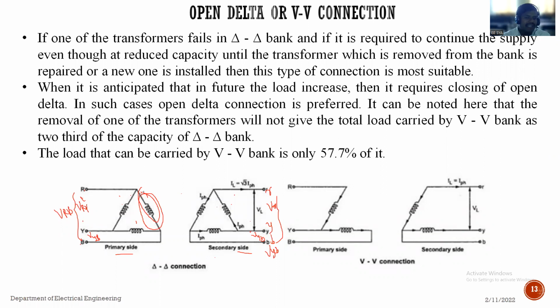Alternatively, we can do like that: suppose if a 3 single phase transformer bank is there, one transformer is taken out for maintenance this month, then it is connected back the next month. Another transformer can be taken out for maintenance, and similarly the next transformer can be taken out for maintenance. This way, we are able to maintain continuity of the supply.